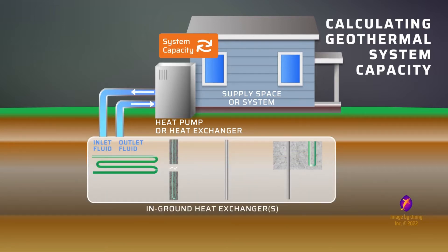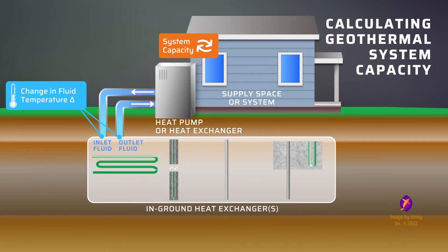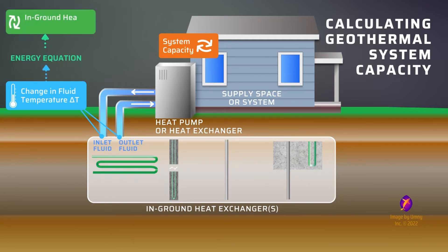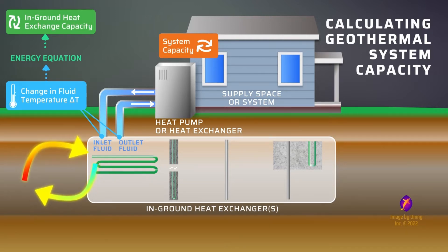This system is connected to the ground using a loop of fluid that branches off into a network of in-ground heat exchangers. There are a growing number of styles of in-ground heat exchangers, and the trends we are talking about here apply to all of them. One of the most important variables in a geothermal system is the change in fluid temperature value. This value can be used with the energy equation to calculate the in-ground heat exchange capacity, which is the amount of heating or cooling the ground is supplying to the fluid entering and exiting the ground loops.